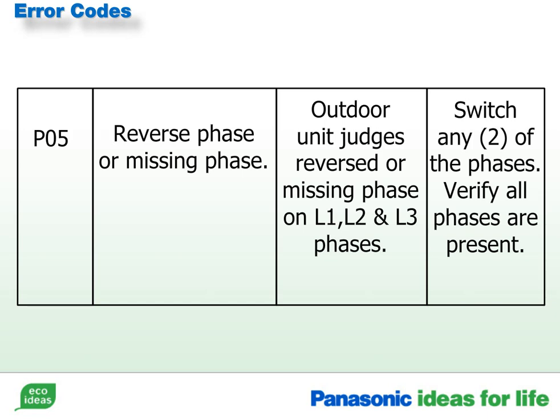Another common error during the commissioning process is a P05. This error will lock out the condenser as soon as power is applied. A P05 error represents a reversed or missing phase. To correct this condition, switch any two phases of the high voltage entering the condenser. Be sure to verify that all three phases are present.